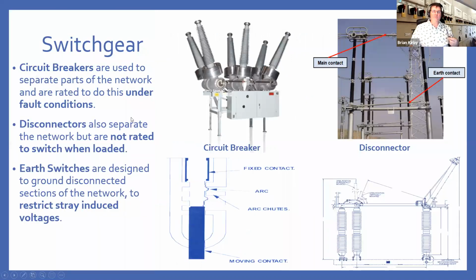Another important part of the network is your switchgear. So you need to know what your circuit breakers are rated for, so that you know what faults you're able to tolerate on the network, or you're able to clear on the network. A circuit breaker, as its name suggests, is simply there to open if you detect a fault and extinguish any arcs, and hence isolate that part of the network.